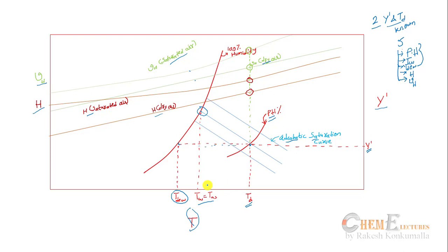Suppose you know wet bulb temperature and dry bulb temperature. First, extrapolate the wet bulb temperature onto the 100% humidity curve. Then follow the adiabatic saturation curve to where the dry bulb temperature meets it — that point on the y-axis gives absolute humidity. From there, extending to the 100% humidity curve gives dew point and percentage humidity, and similarly humid volume and enthalpy.